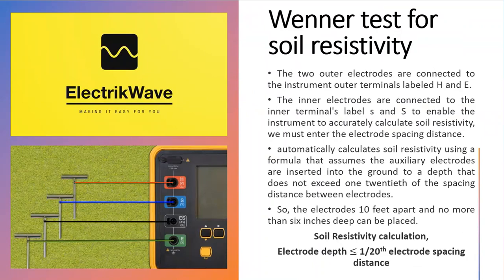The two outer electrodes are connected to the instrument outer terminals, labeled H and E. The inner electrodes are connected to the inner terminals, labeled S and ES. To enable the instrument to accurately calculate soil resistivity, we must enter the electrode spacing distance. The instrument automatically calculates soil resistivity using a formula that assumes the auxiliary electrodes are inserted into the ground to a depth that does not exceed 1/20th of the spacing distance between electrodes — so the electrodes 10 feet apart and no more than 6 inches deep.